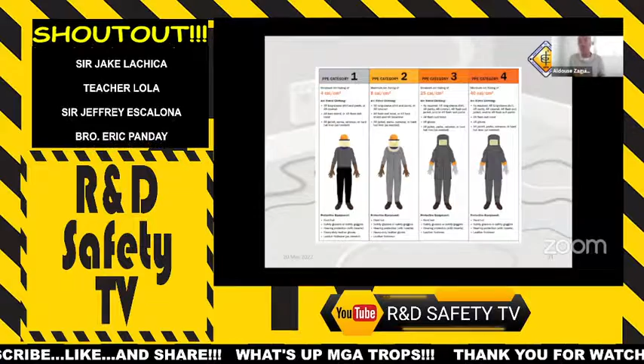You've got the head protection, you've got the face shield for arc flash, and then you've got the eye protection there. Now, the usual complaint about the face shield is that it's dark, right? Our electrical rooms are not well-lighted. They're not as bright as offices. Okay? But it has to be amber, it cannot be crystal clear like his goggles. Because of that flash, you also have to protect the person's eyes. Okay? You've got the head, face, and neck protection. So you've got this hood on the body, you've got the suit, rated category 1, 2, 3, and 4.